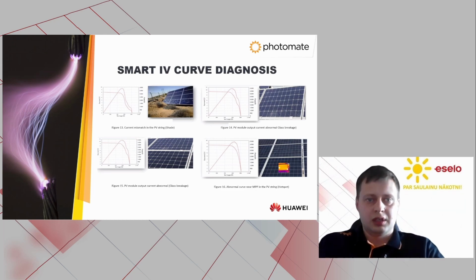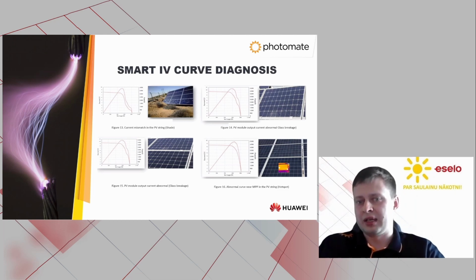In contrast to the traditional IV curve testing methods, which require a physical site visit and disconnection of the inverter to measure each string individually, the smart IV curve diagnosis feature can be performed remotely. This results in a significant reduction in time and cost. One key advantage of the smart IV curve diagnosis feature is its ability to detect hotspots, which decrease module efficiency and in extreme cases can pose a fire risk.